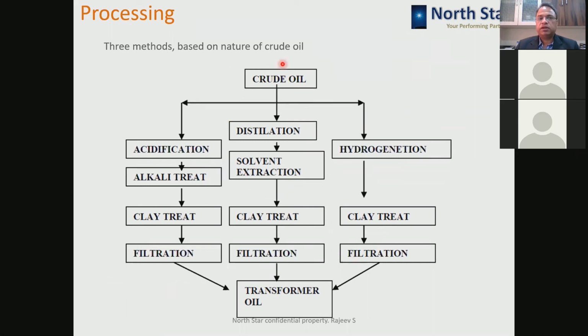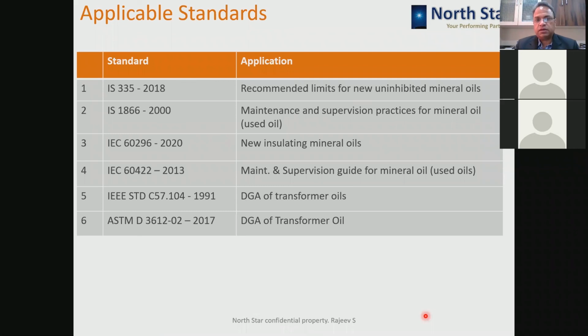So depending upon the properties of crude oil, any of these three processes are used for the distillation of the transformer oil. So what are the standards which are used for mineral oil? IS 335:2018, the recommended limits for new and uninhibited mineral oils, is mentioned in IS 335. So please note, when you are purchasing a new oil, fresh oil, then IS 335 is applicable.